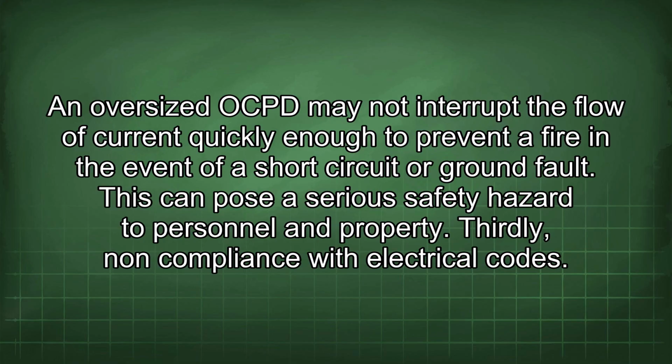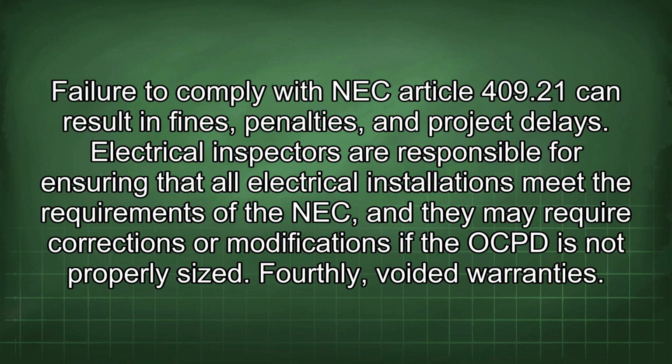Thirdly, non-compliance with electrical codes. Failure to comply with NEC Article 409.21 can result in fines, penalties, and project delays. Electrical inspectors are responsible for ensuring that all electrical installations meet the requirements of the NEC, and they may require corrections or modifications if the OCPD is not properly sized.